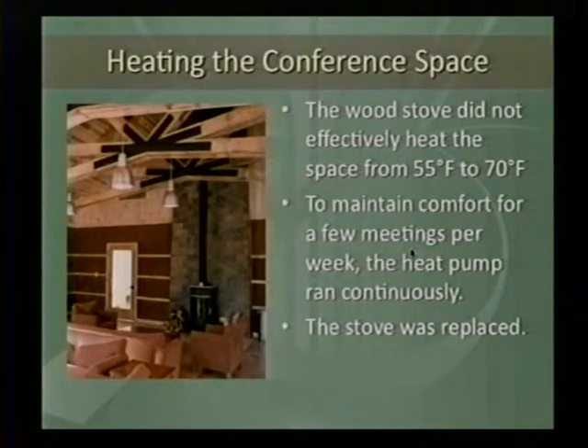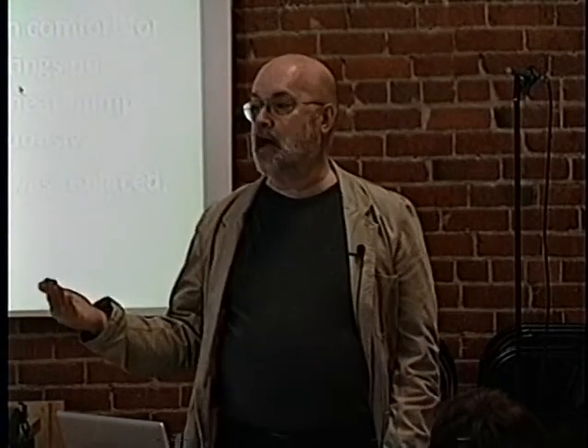side with the client. The conference space had this elegant wood-burning stove in it, which was a lousy performer. And it couldn't bring the temperature up from the 55 to 70 degrees. So in the first year, the heat pump was running 100% of the time because they were trying to use it to heat up the space. We designed the heat pump for this space, on the design condition, it was sized to bring the temperature to 55 degrees. That was it. We did not put a factor of safety in on the equipment. We're mucking around with how you size equipment from simulation models and whether or not it is a good thing to oversize HVAC equipment in buildings or not.